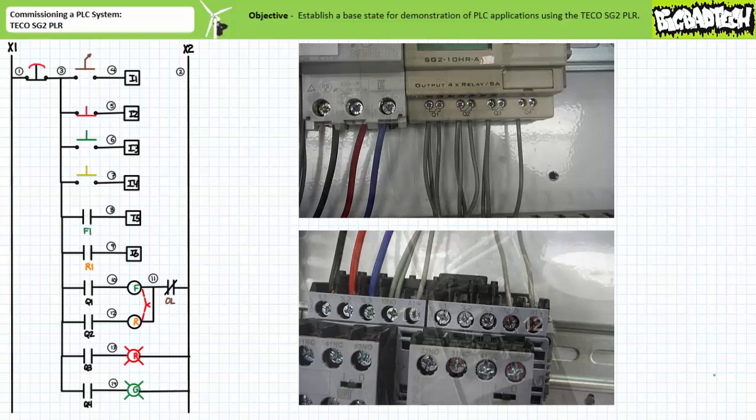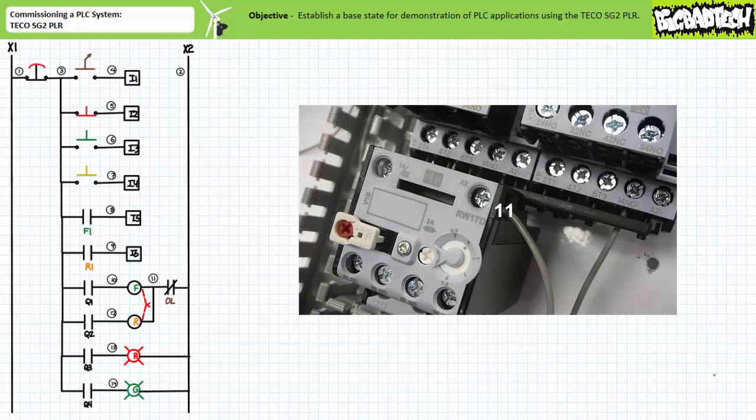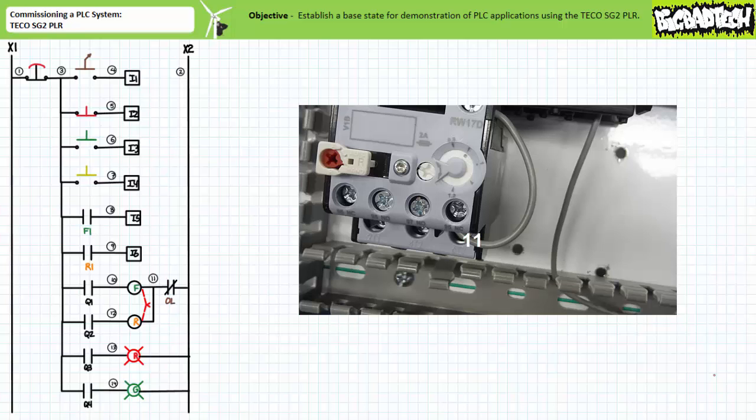Outputs Q3 and Q4 are respectively routed to the red and green pilot lamp X1 terminals using wires 13 and 14. Given the reversing wire kit has conveniently already conjoined the A2 terminals of both the F and R contactor coils, wire 11 comes out of the conjoined A2 terminals and goes right into the conveniently available 95 terminal of the normally closed overload.